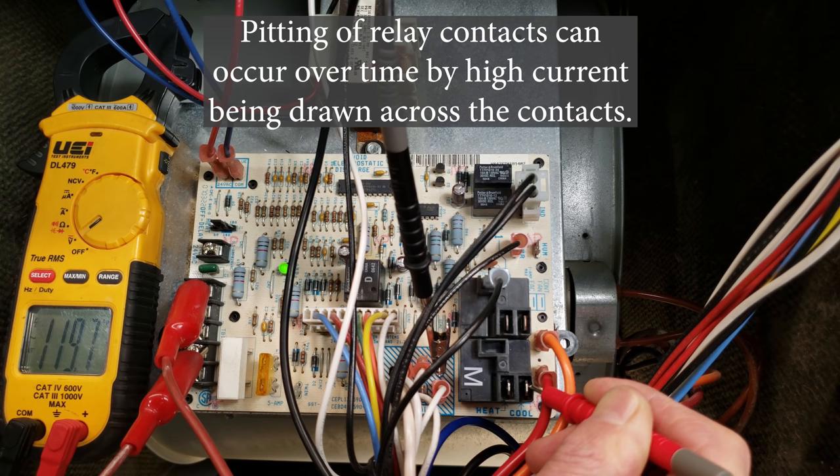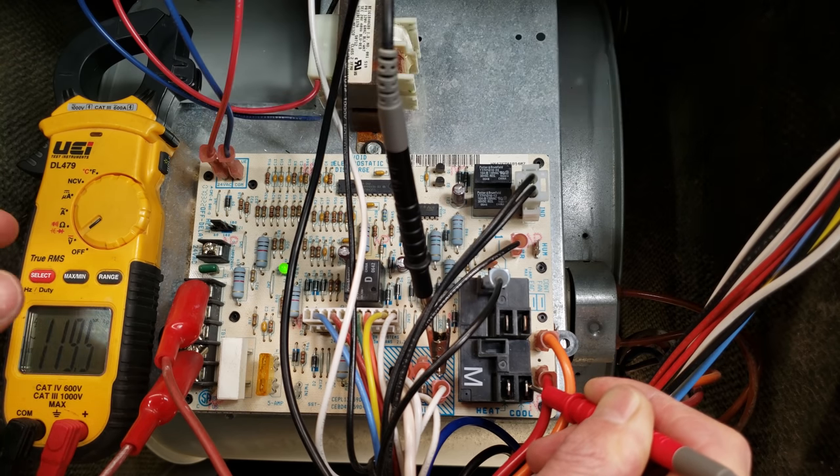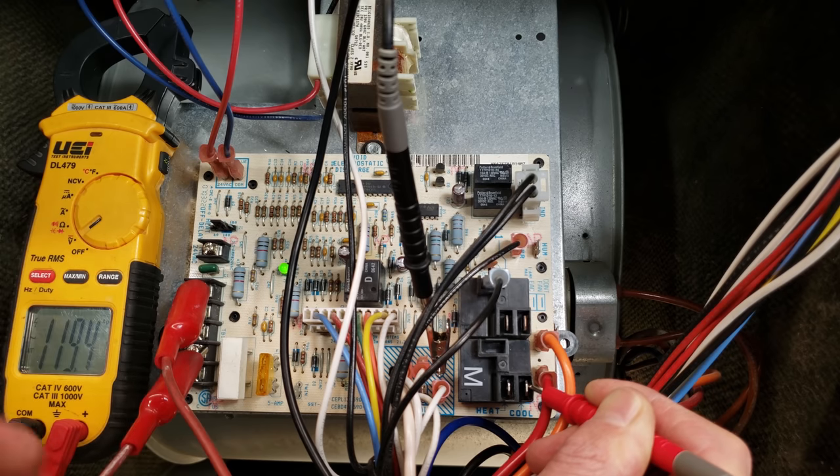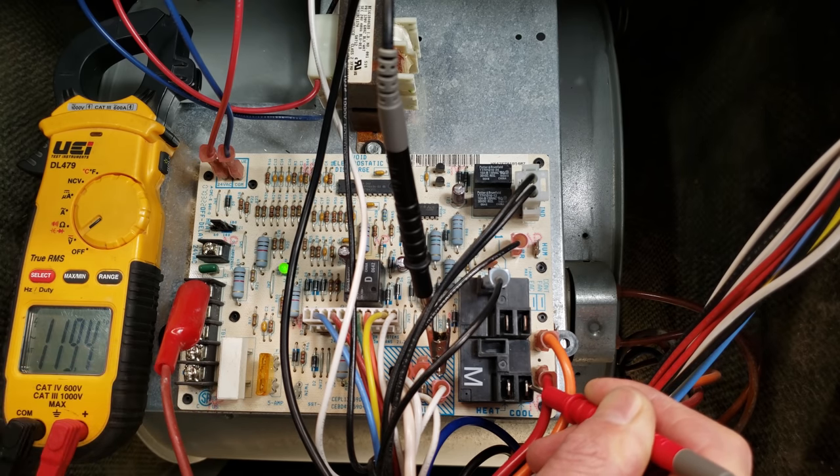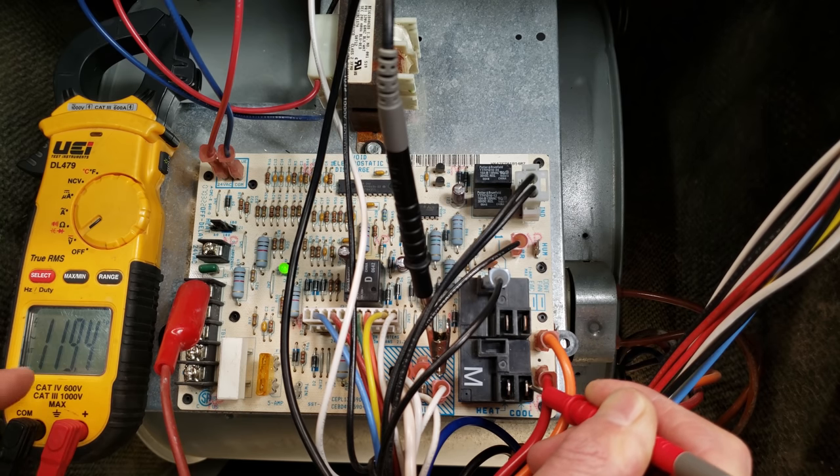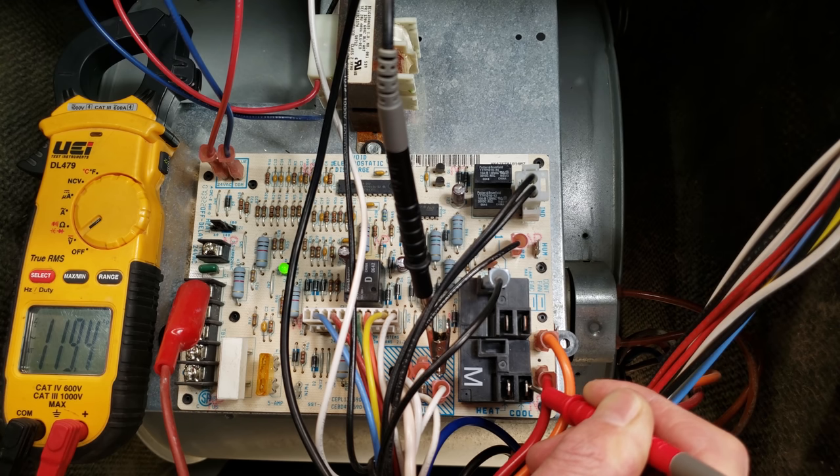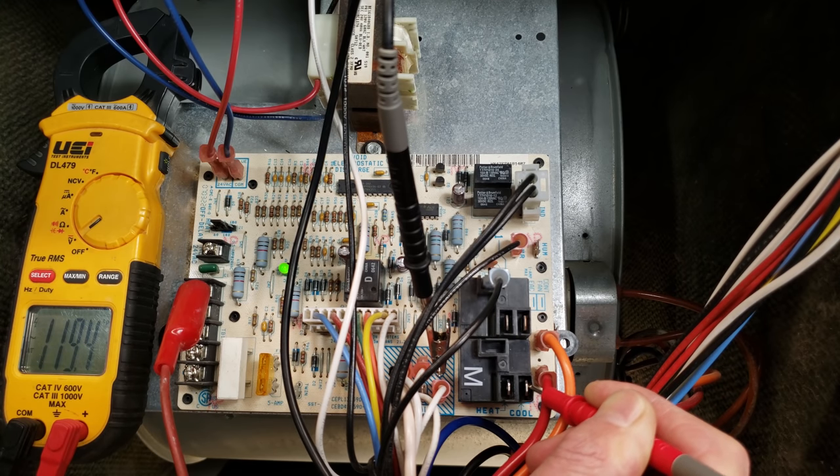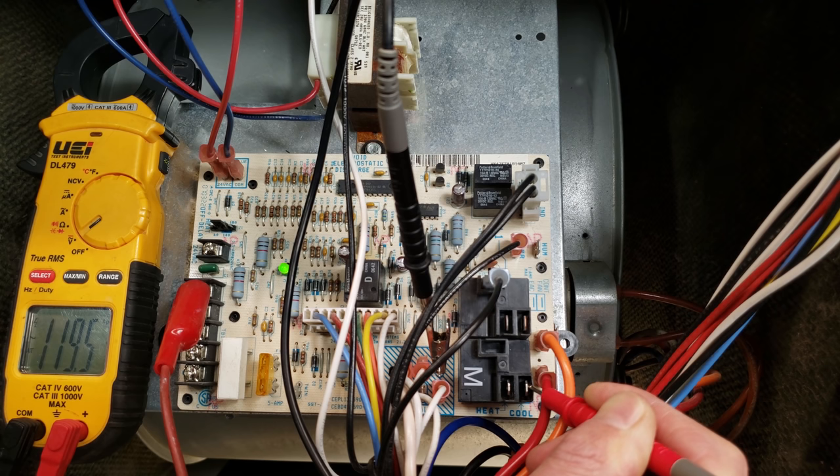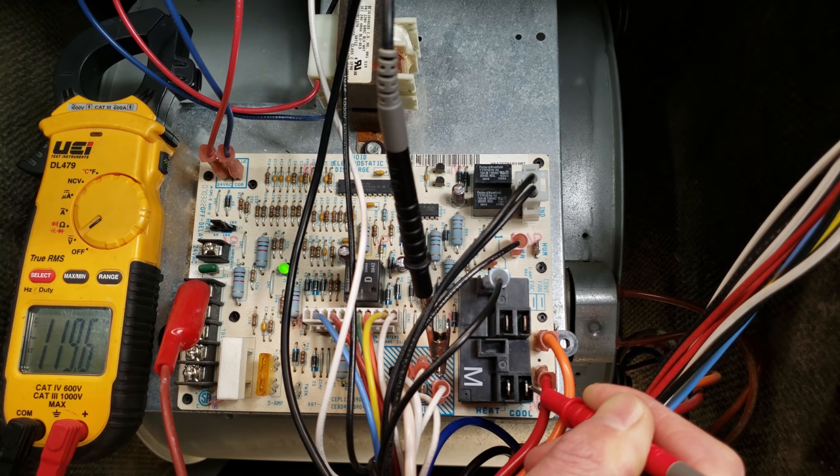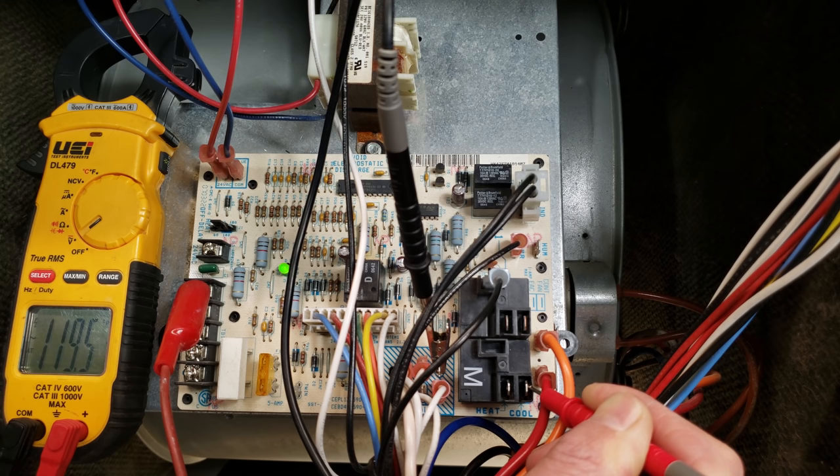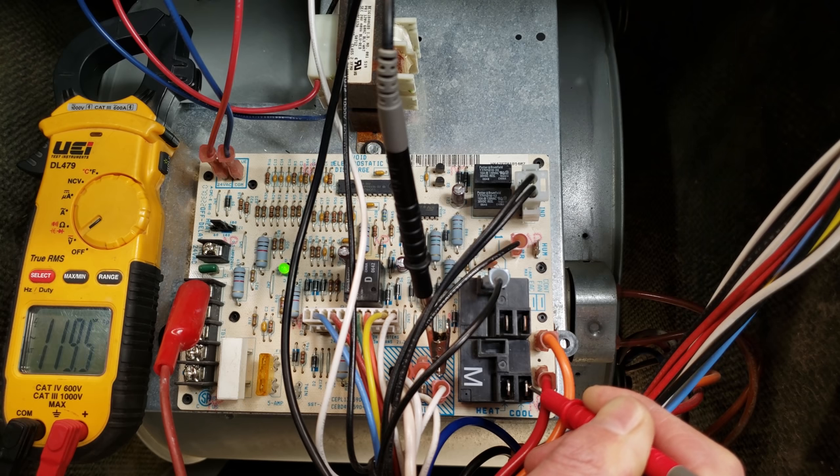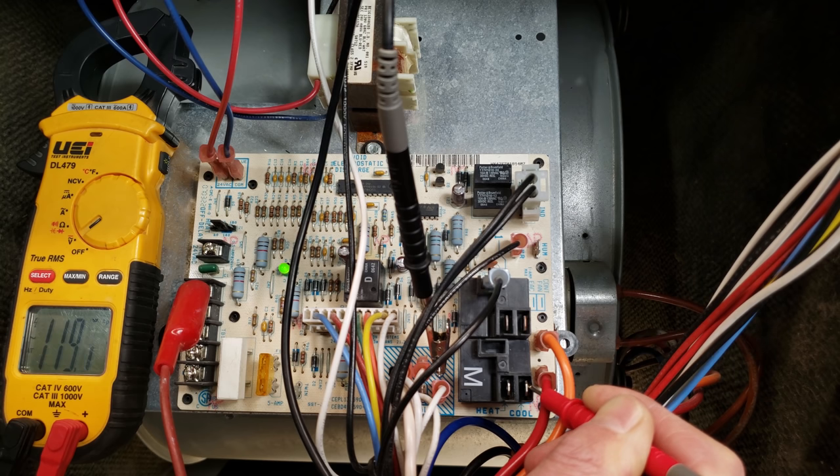Before we move on, I want to make sure you're aware that anytime the thermostat reaches the temperature you're trying to set and it no longer needs air conditioning to run, the R and Y are going to disconnect so you're no longer going to have your 24 volts on the Y terminal, but you are going to still supply power to the blower motor. As you can see we still have 119 volts and that's because there's a blower off delay built onto the board. It's a timing mechanism that's going to allow power to the blower motor for maybe an additional 30 or 60 seconds after your outdoor compressor turns off. That's because your evaporator coil is still low in temperature and there's still a lot of condensation on it, so you're going to continue to run the blower motor to rise the temperature of the evaporator coil up and dry some of that condensation off. After that 30 or 60 seconds then it's going to shut off power to the blower motor.